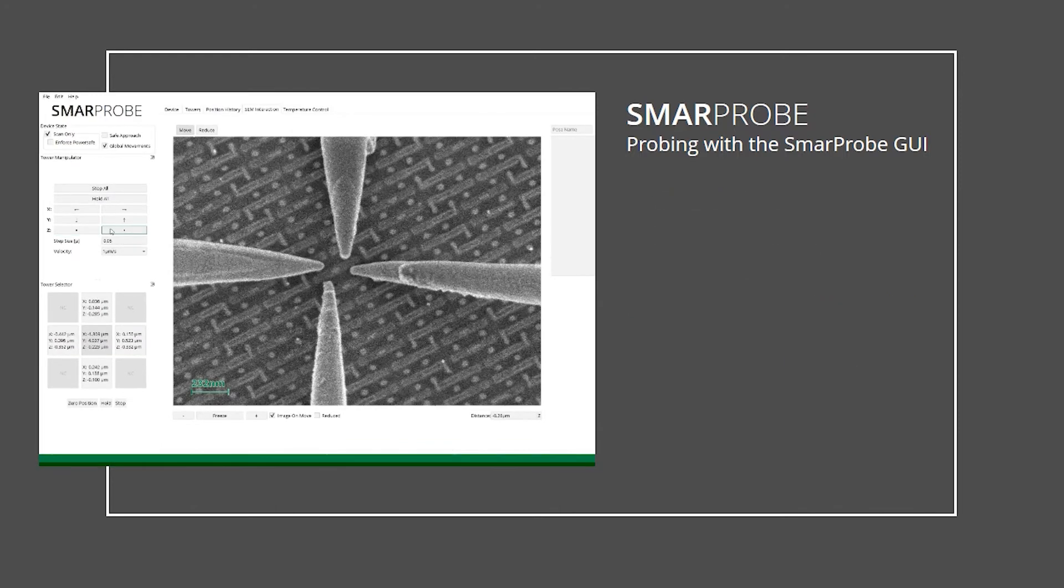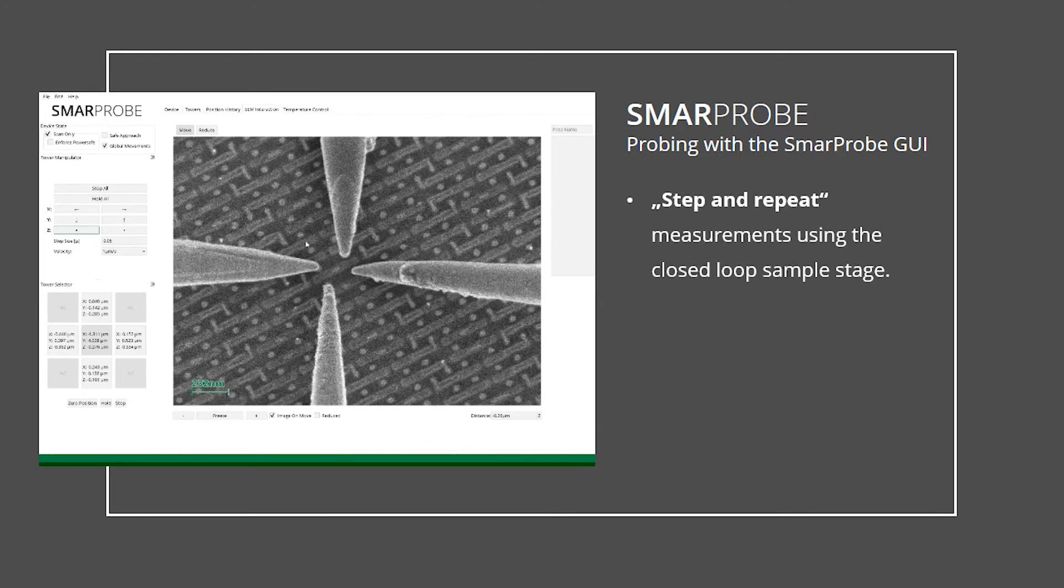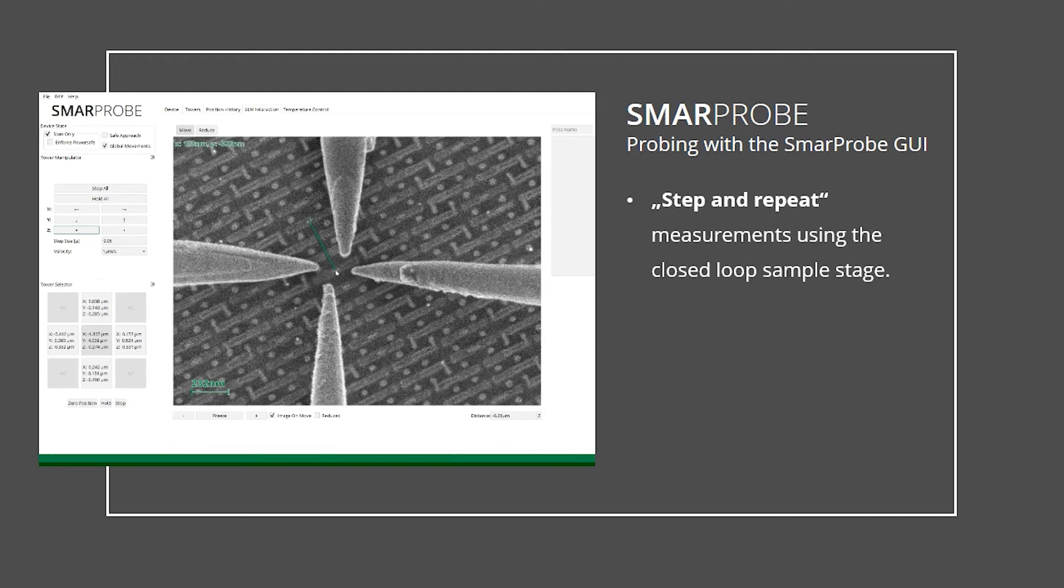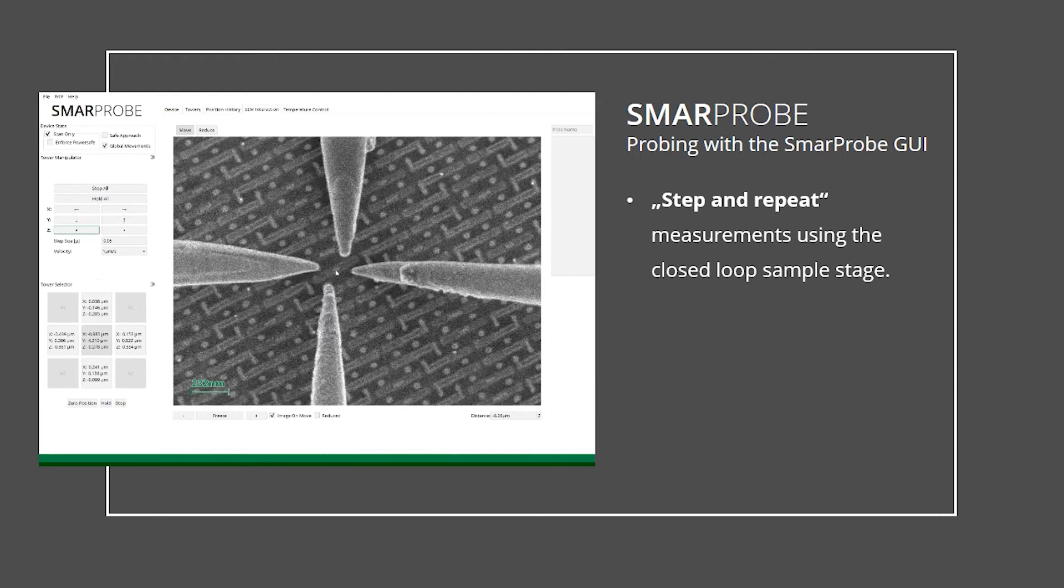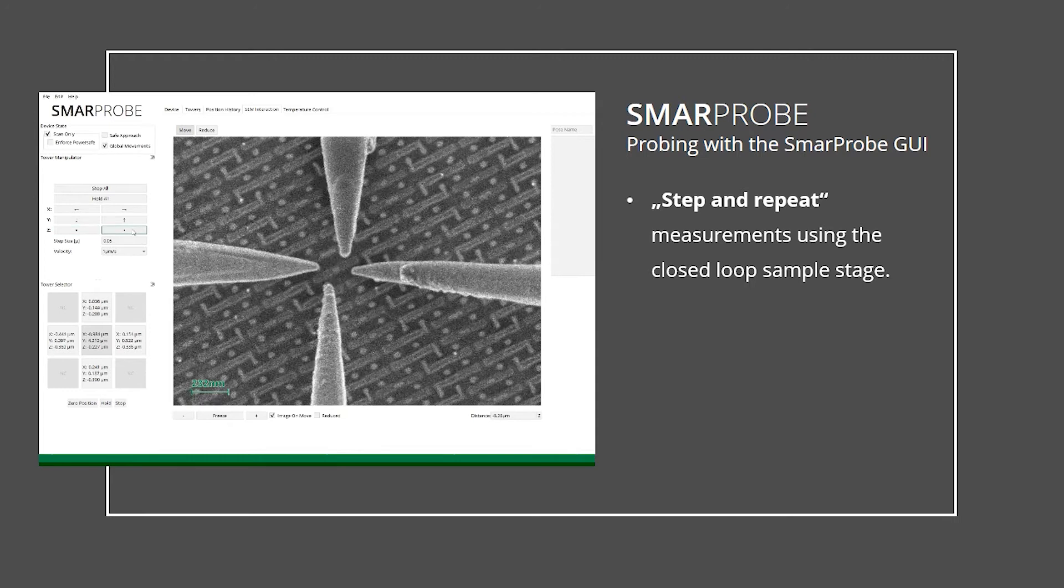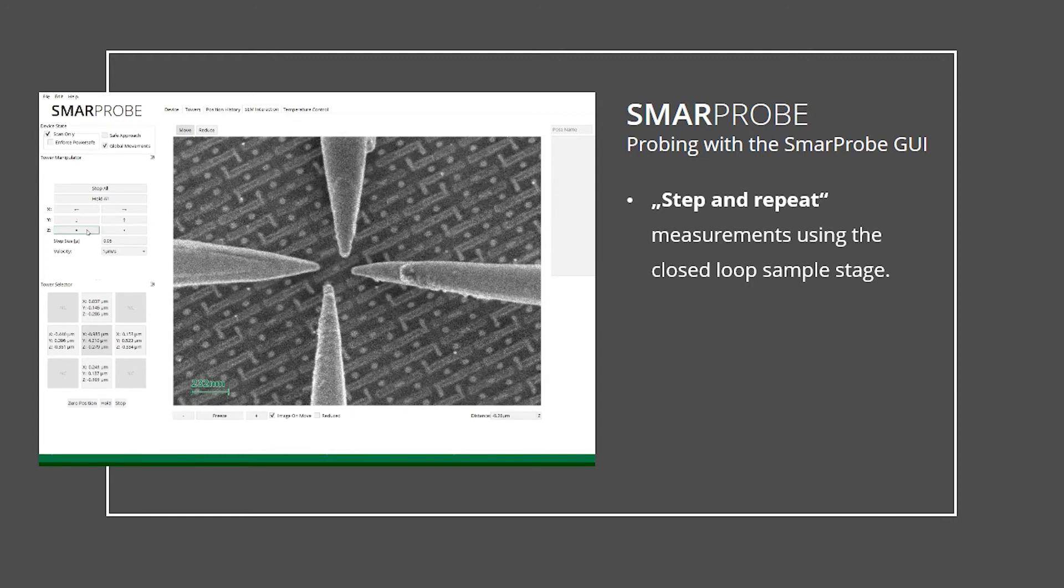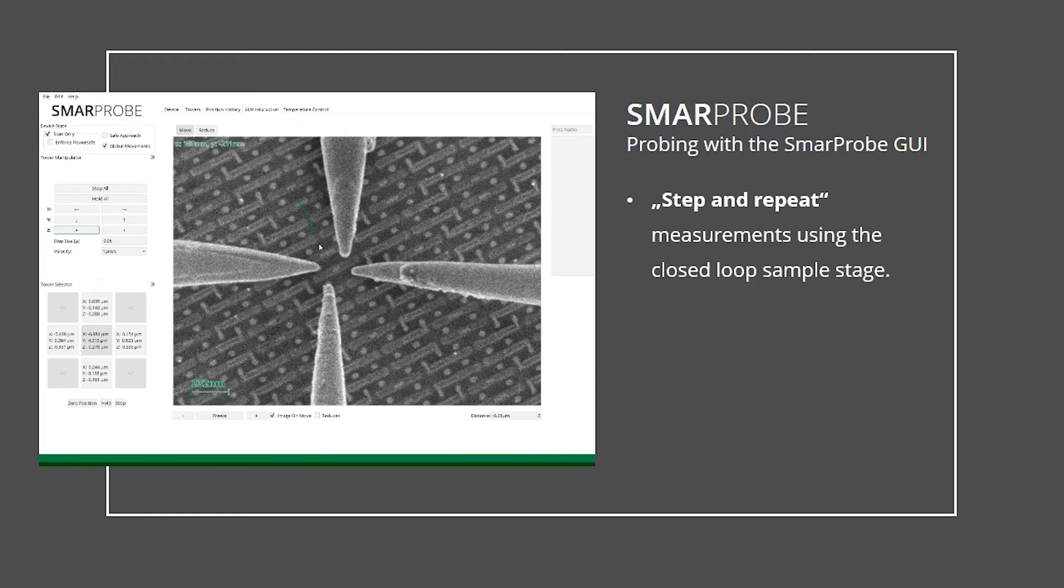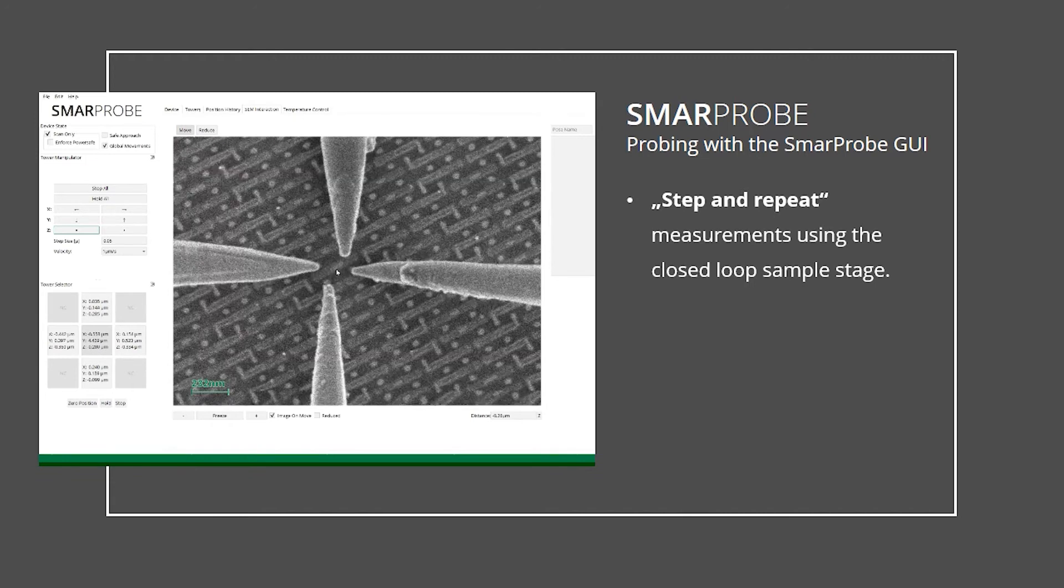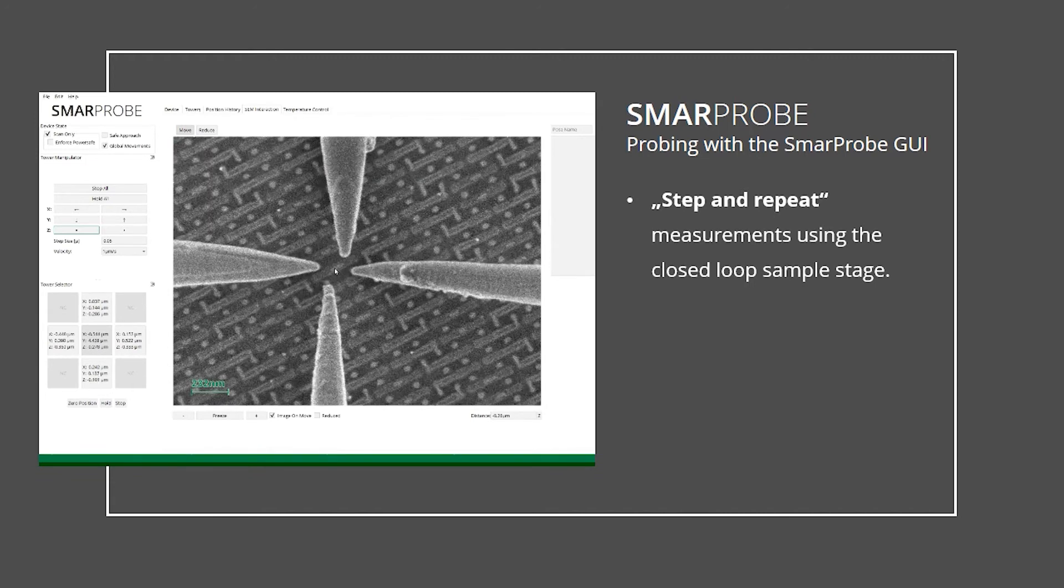In case of periodic test structures, the closed-loop control helps to speed up the test process by performing step-and-repeat measurements. In this case, the manipulators do not move, and only the sample stage performs defined movements from one test structure to the next.